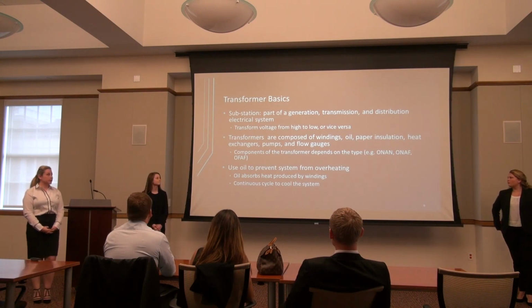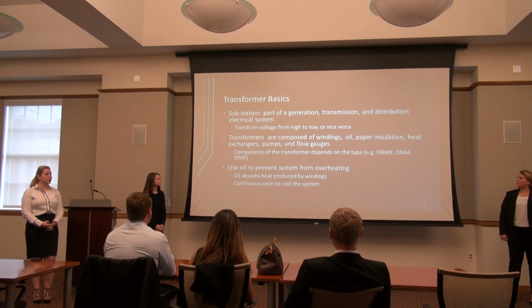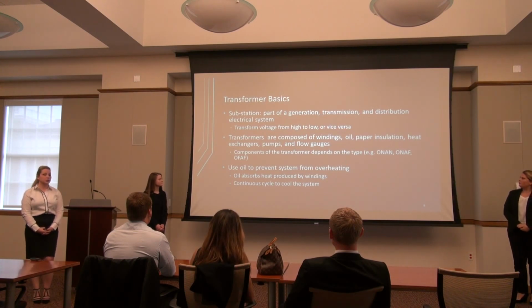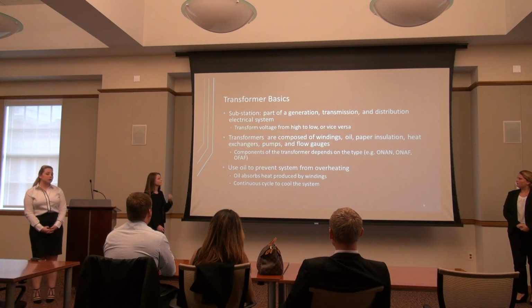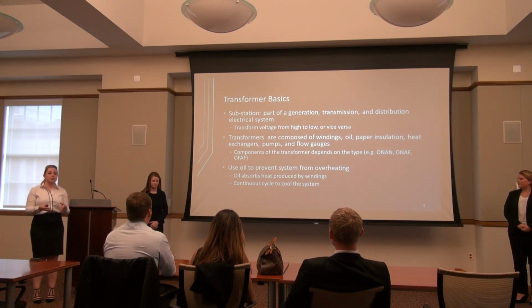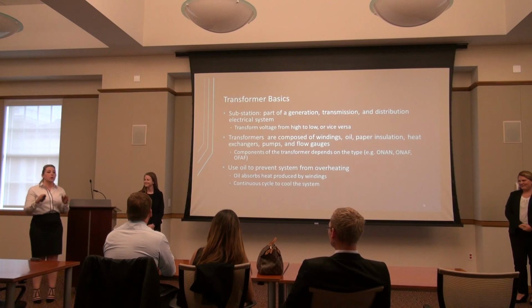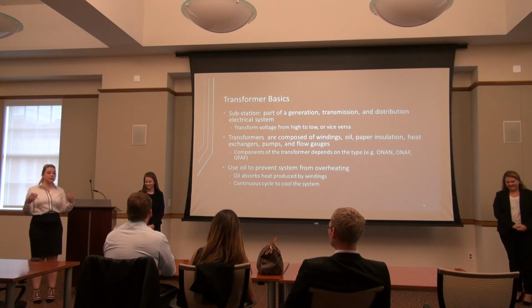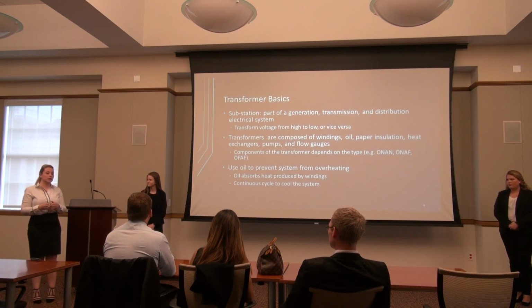So oil natural air forced transformers are composed of windings or coils, oil, paper insulation, heat exchangers, pumps, and flow gauges. How a transformer works is that the coils produce heat and the oil absorbs this heat, causing it to become less dense. So it rises to the top of the transformer and overflows into the radiator and into the radiator tubes. When the oil comes in contact with the air at the top of the transformer, the heat is then transferred to the air, causing the hot air to rise and be replaced by cooler air, which creates the air circulation, which, as I mentioned before, is also perpetuated by the fans. Now that the heat is no longer in the oil, it becomes denser and sinks back down to the bottom of the transformer, and this process continues, keeping the system cool.